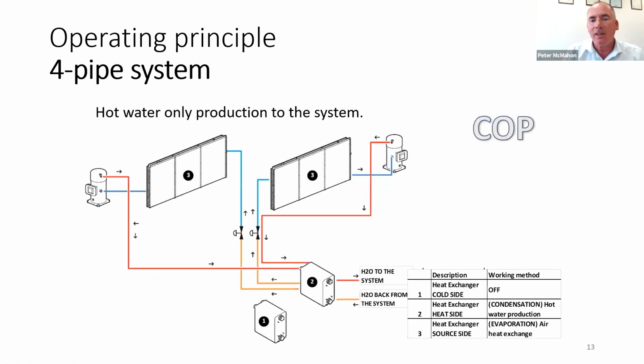Now, let's say it's the winter time, you have a heating requirement, you may not have a cooling requirement. So now what we're doing is we're dedicating both circuits purely to heating. The evaporator, the cooling is off. So again, we have our compressors pumping our refrigerant down through the condenser or recuperator, depending on the terminology you prefer. Goes back down through the expansion valve. What was a condenser is now the evaporator. It's basically a reverse cycle. And back to your compressor.